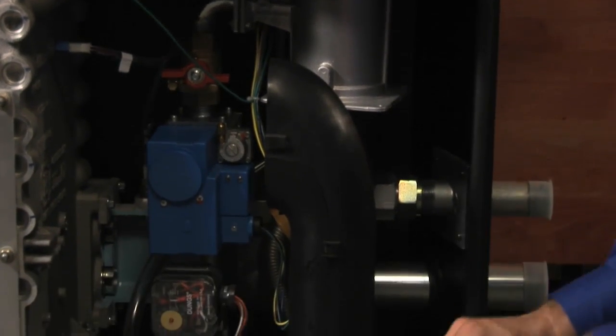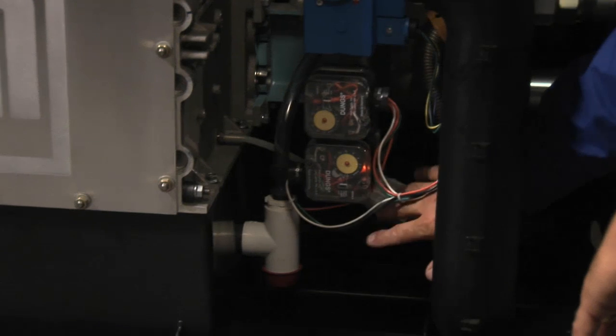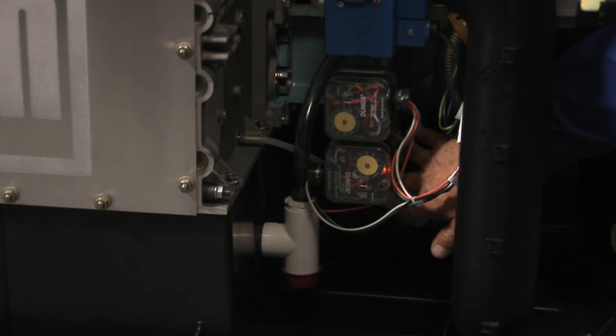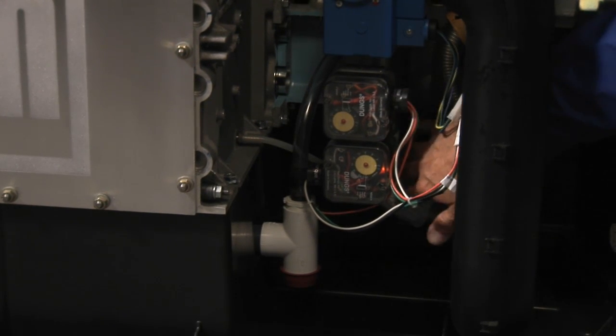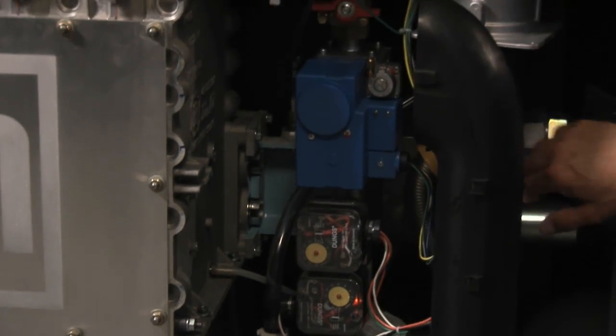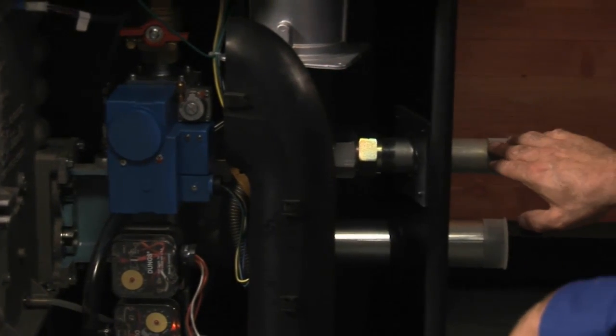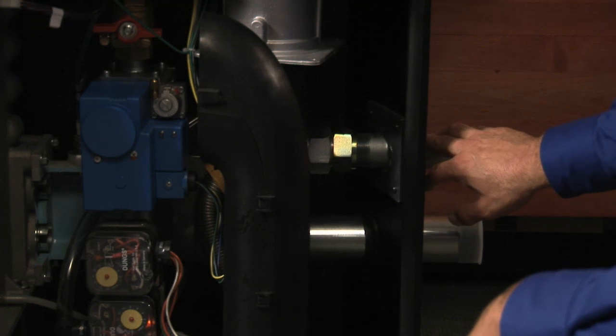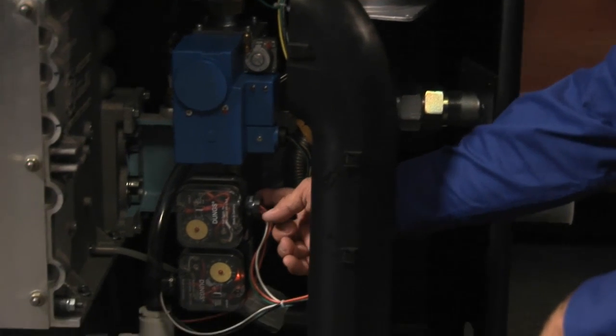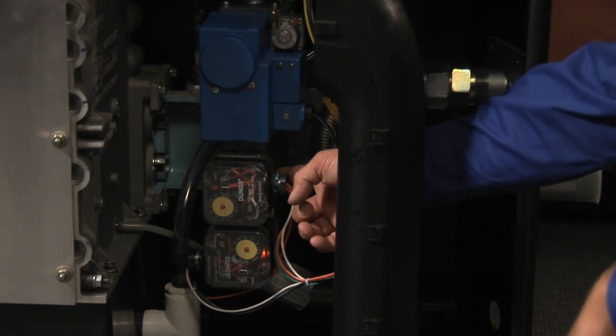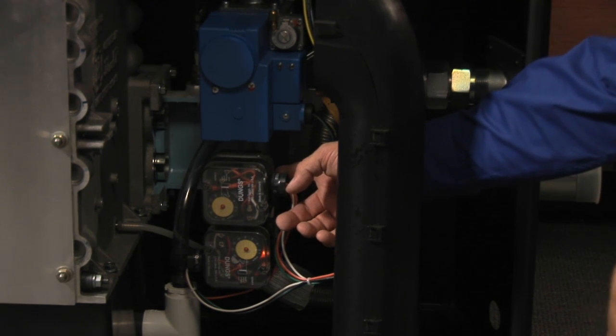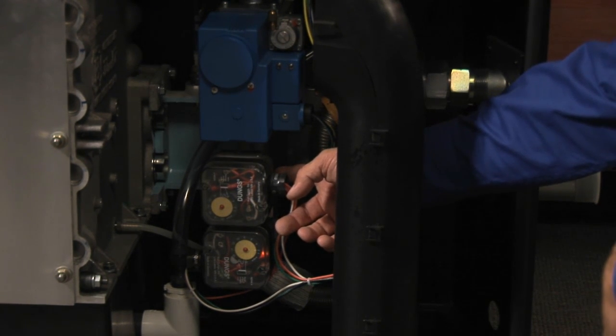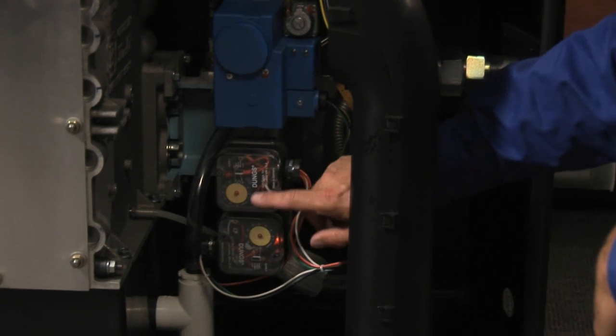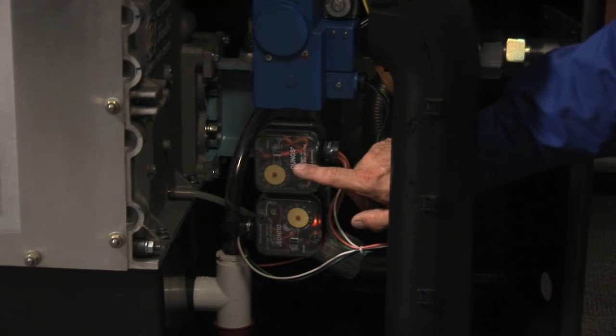Coming out of the bottom of the low pressure switch, we drop down off of the header here, come down around, and we have a flex line to the gas pipe coming out of the side of the boiler, 1.25 inch gas pipe. There's also, right behind the high pressure switch, a plug. This is where you would get your incoming gas pressure readings.